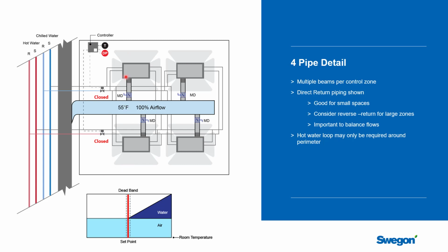And again, we're showing direct return piping through here, but reverse return piping would be fine. And as this zone gets bigger and you have more and more beams in it, reverse return piping would actually be advantageous just to keep the flow rates balanced.